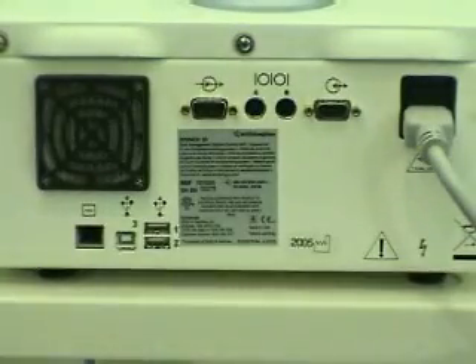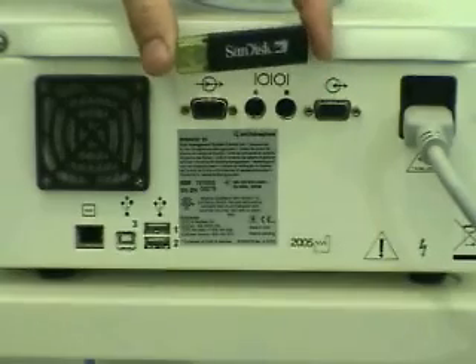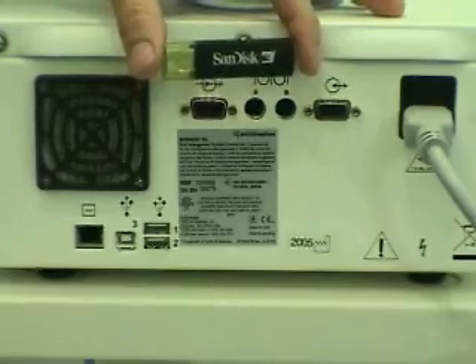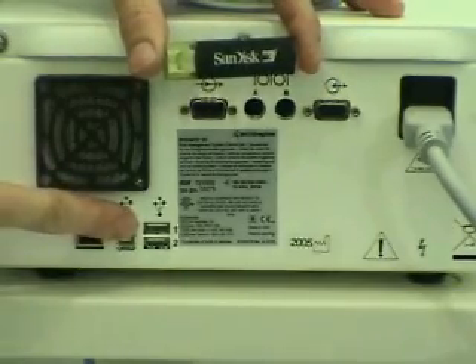So one very useful feature of the DYONICS 25 is the ability to check the performance of the transducers in the field. This can be of value obviously to biomeds in facilities that want to test out the pump, but also for you as a rep if you have any reason to believe that the transducers may have failed. And the way you can do that is to use a Biomed test key that comes with the pump, which you would insert in this USB port down here.